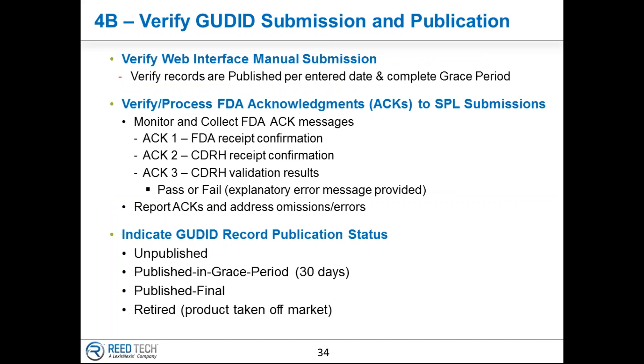It is important to verify that the data actually made it to the FDA. You want to make sure records are showing up as published. The FDA is allotting a 30-day grace period where you can make some edits, except for the published date field. After that period, a number of data fields become fixed. Verifying that acknowledgement for SPL submissions is a little different — there's an XML acknowledgement file returned from the FDA. Make sure your system properly addresses those acknowledgements: there are three separate events acknowledged by the FDA.